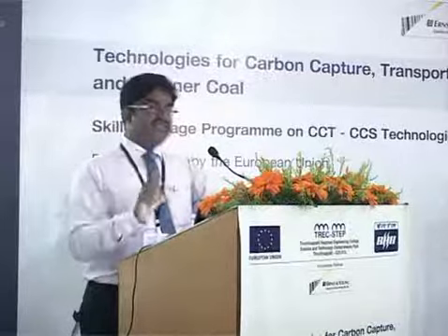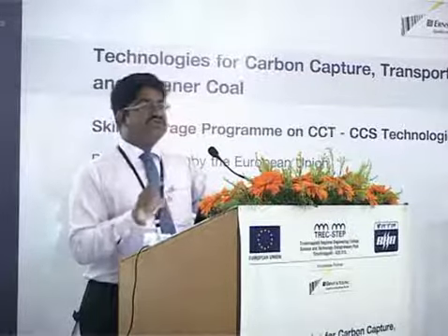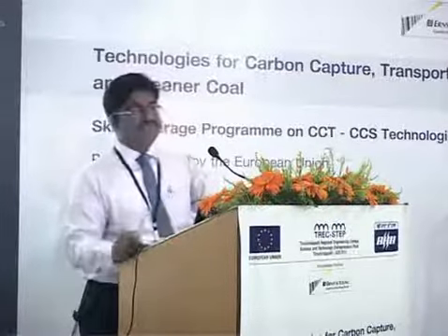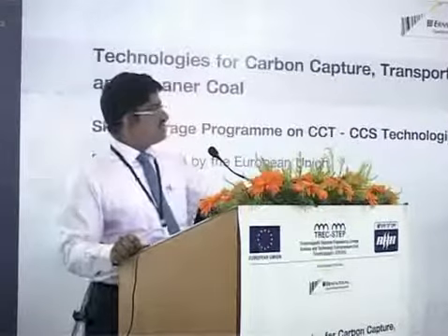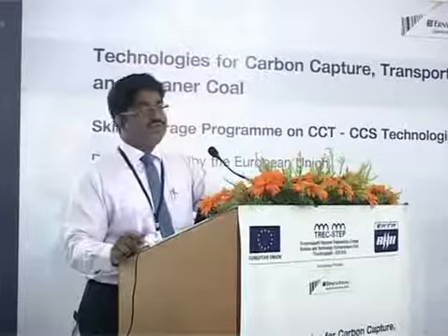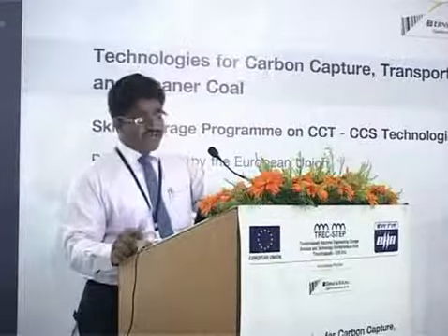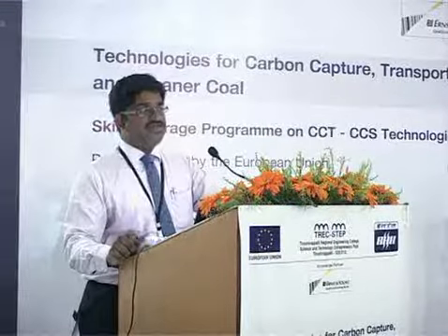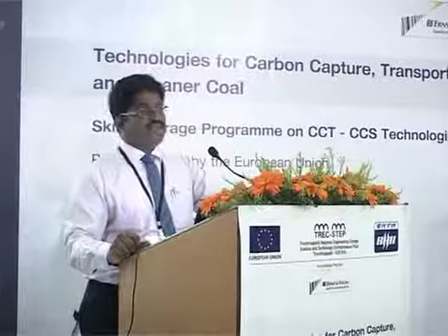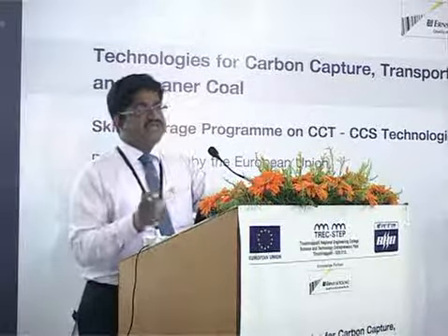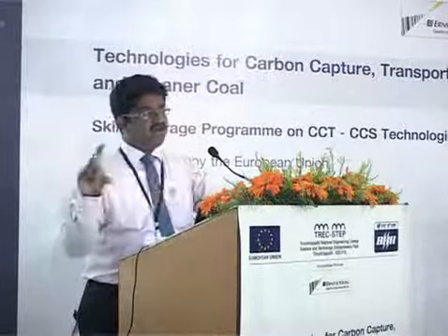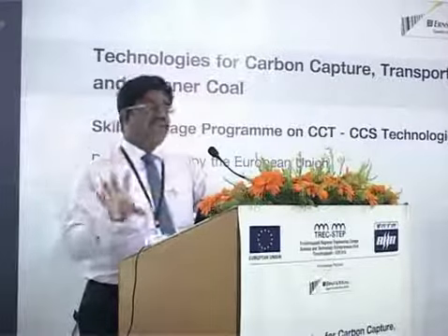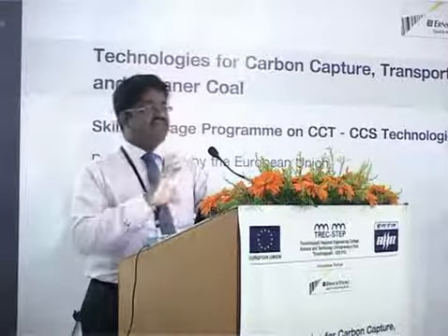But specifically in this case, we have to come out with the levelized cost of generation. If you see here, the levelized cost of generation for a subcritical power plant is only 2 rupees 2 paise, whereas for a supercritical power plant it's about 2 rupees 14 paise. This levelized cost of generation is being calculated for 20 years, considering similar interest rate, payload, etcetera.